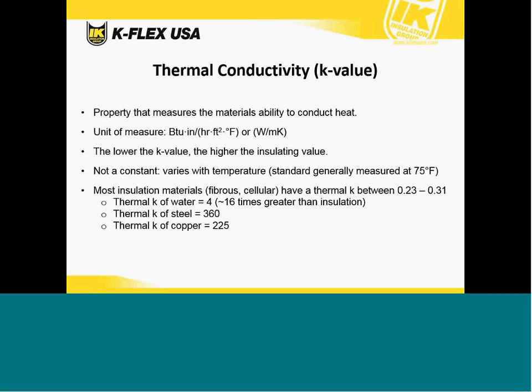It's also important to remember that it's not a constant. It varies with temperature. Insulation materials are generally measured at 75 degrees Fahrenheit, but can be measured at different temperatures, including 32, 100, and 200 degrees Fahrenheit. So when comparing insulation materials, it's important to compare K values measured at the same temperature. Insulation materials have a thermal K between 0.23 and 0.31, which is a fairly tight range when you consider the thermal K of other materials such as water, which is 4, and we'll get more into that in a little bit. Thermal K of steel is 360. K of copper is 225. Above a certain point, materials stop being insulators and become conductors, such as copper and steel.